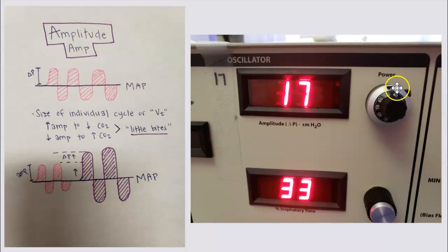This little black piece goes up. And then to the right is to turn the amplitude up. To the left is to turn it down. And then when you are charting, you would see there's a number in this little window right here. And then these. So I would chart my power as maybe 1.4 or 1.5. It's right in the middle, so take your pick. That is my power that I'm using to drive my amplitude. So that is amplitude. And then I just lock it again.